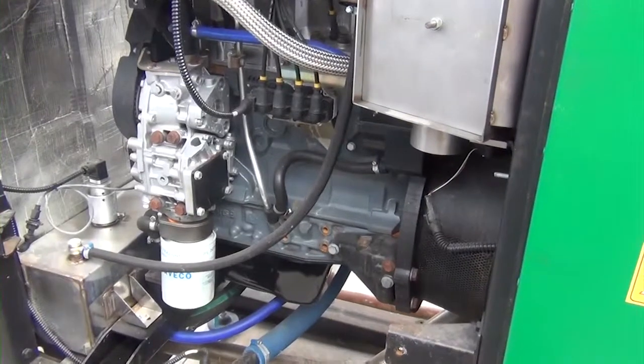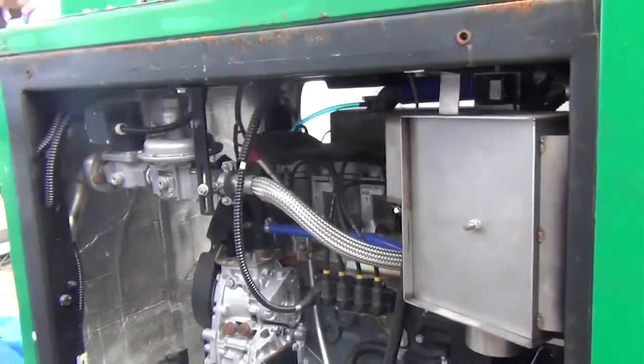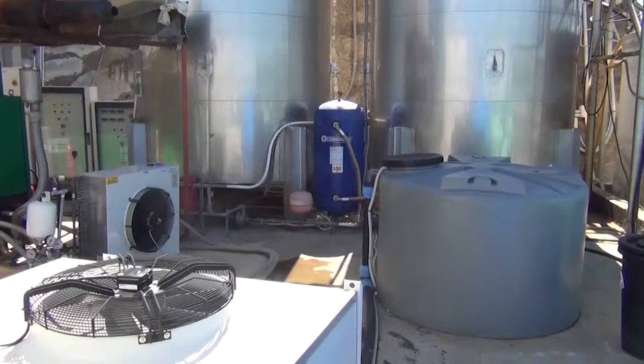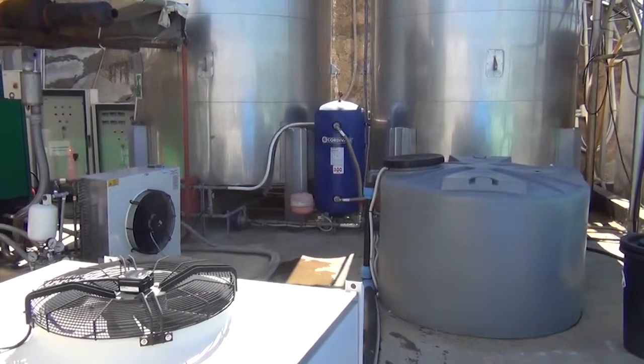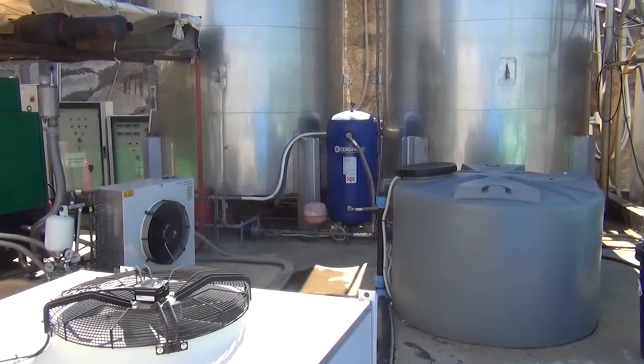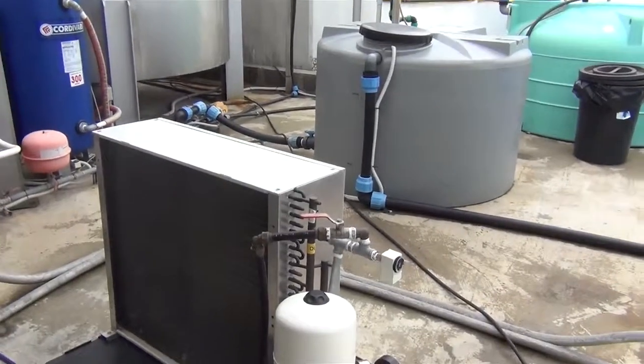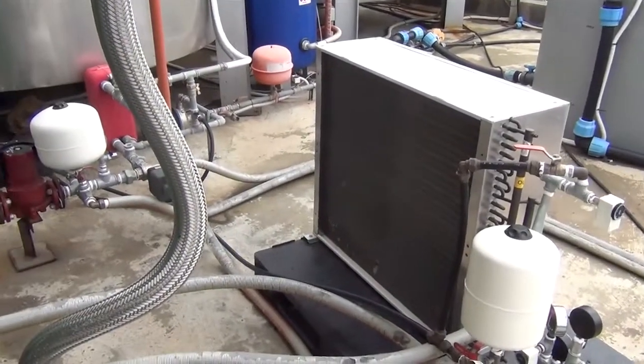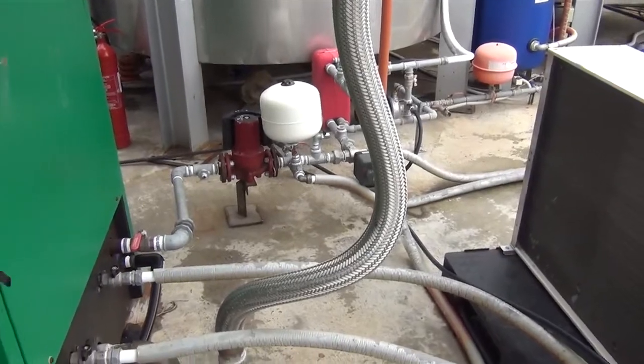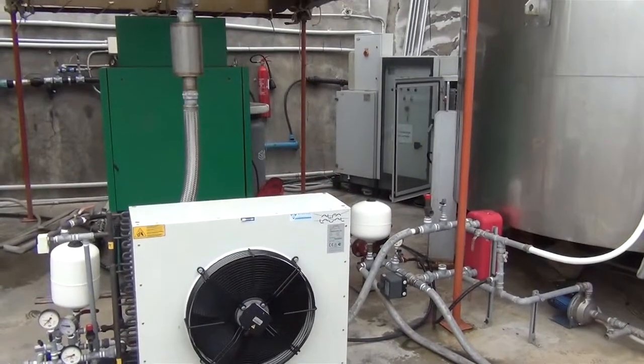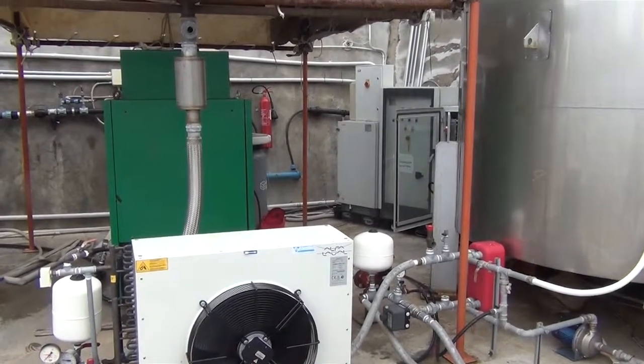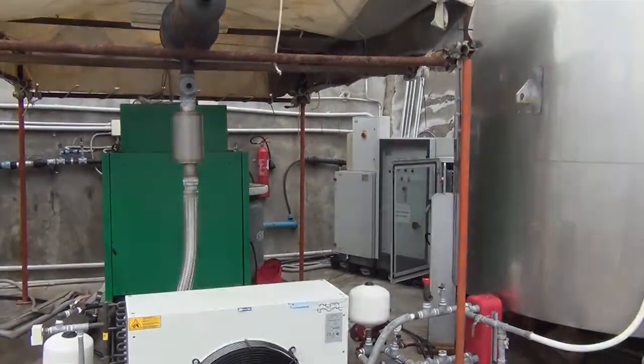In the hydraulic circuit of the motor, cooling water outlet temperature is 80–85 degrees. The water circuit transfers the accumulated heat to the hydrolysis tank. It was necessary to install a heat sink to ensure the cooling of the liquid in case of insufficient heat exchange for the hydrolysis, in order to have a lower return temperature of the liquid, 73 degrees.